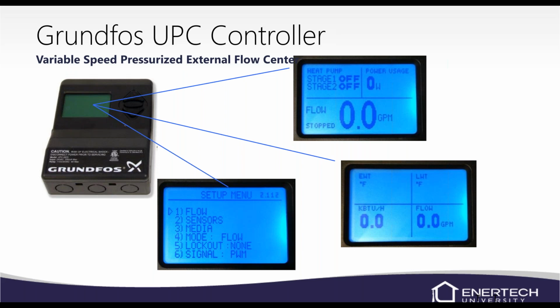If you get it just for flow, it'll just run the controller based on flow itself, so GPM. If you ever look at the heat of extraction, the number that you calculate and the number that this controller calculates could be a little bit different. This controller does use the exact specific gravity for the type of antifreeze that you put in. So where we say 485 is a good number any time we're using antifreeze, propylene glycol is actually 483, so it will use the 483 calculation rather than the 485. Your hand calculation could be a little bit off from what's on the screen. Not really too big of a deal unless you get outside of your parameters.